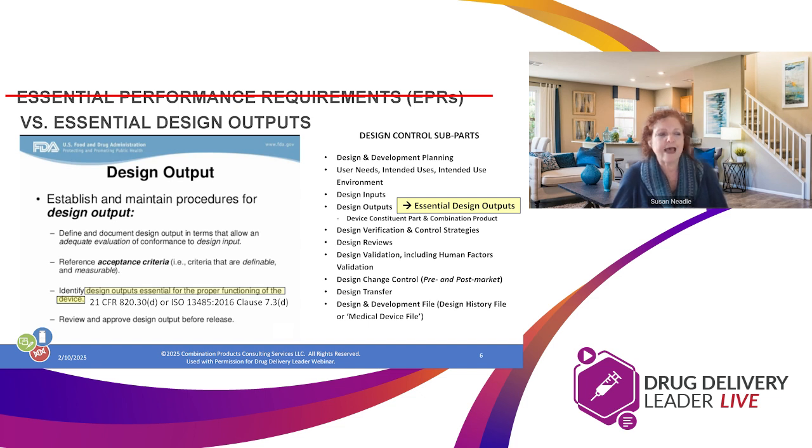Now, when I look at that, hey, wait, the FDA started introducing this term, essential performance requirements, and industry really got very confused about these essential performance requirements. So in trying to clarify it during the last webinar, we talked about, well, there's this new term that got identified called essential design outputs.